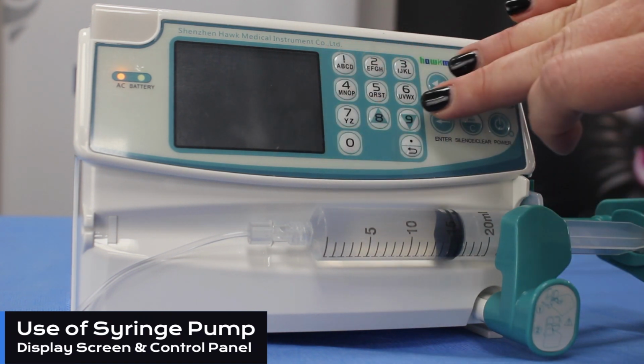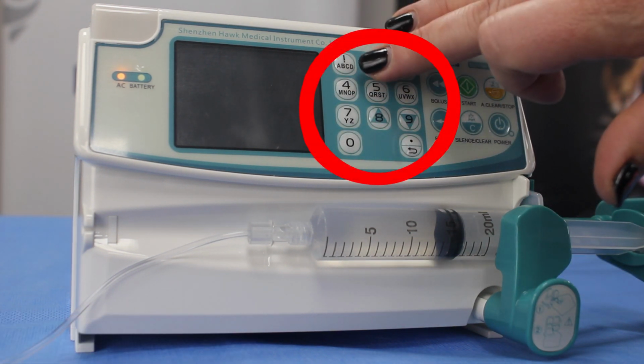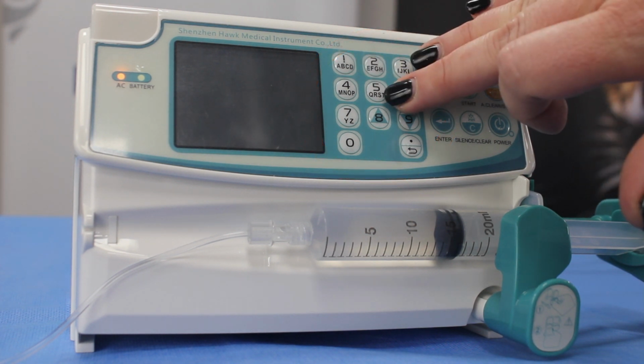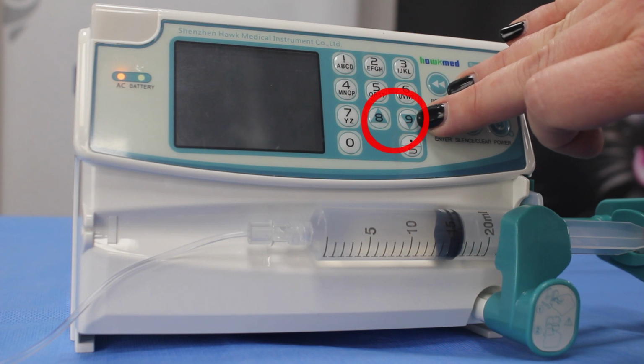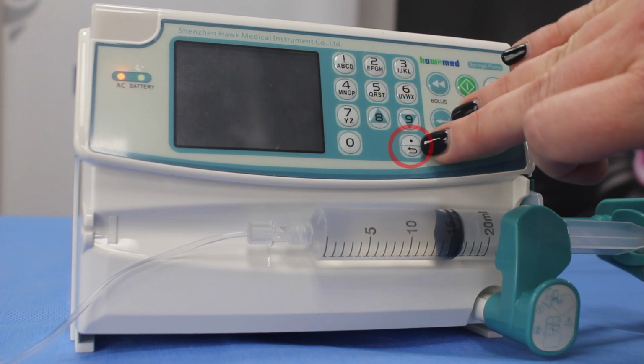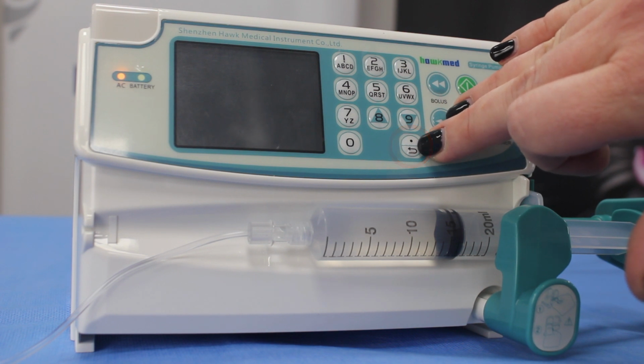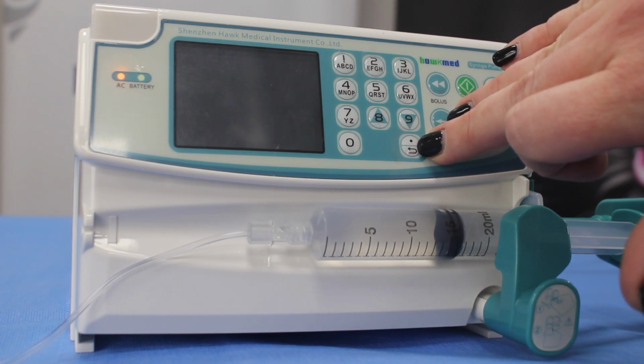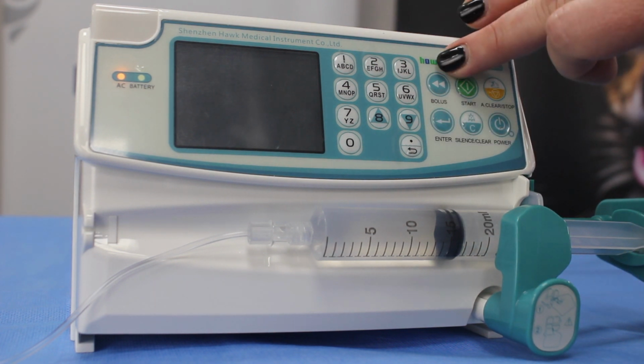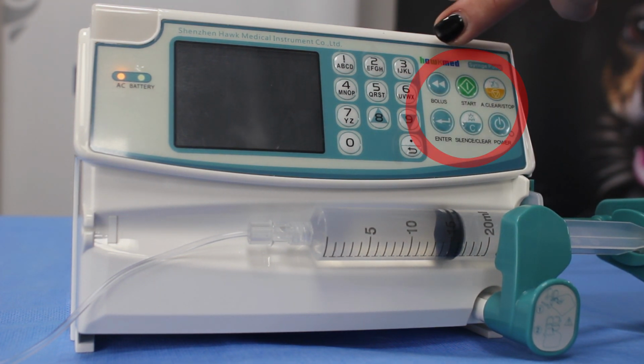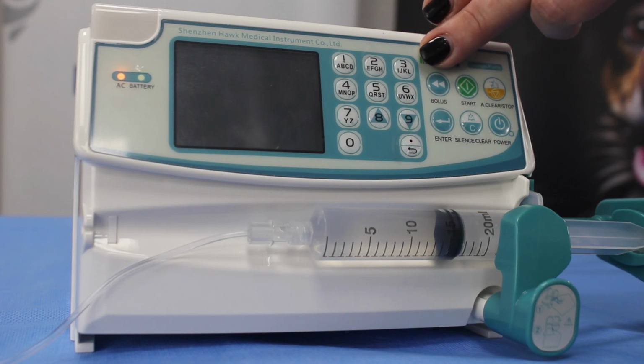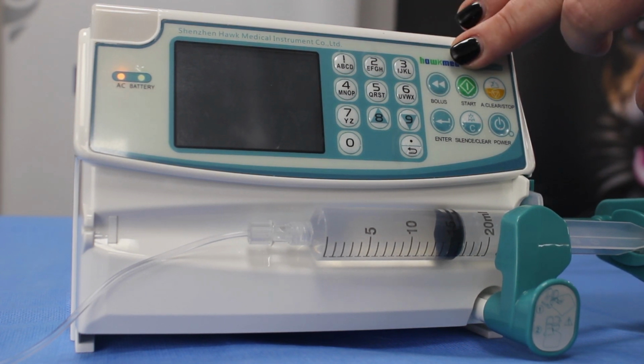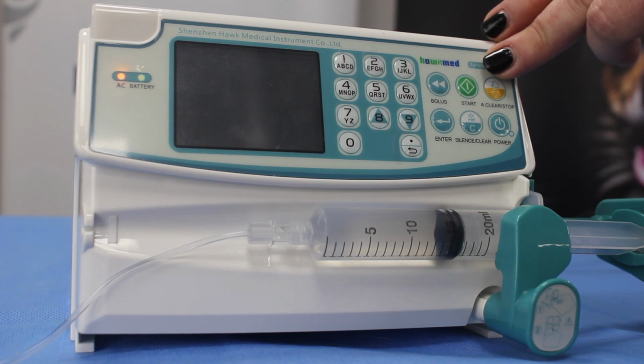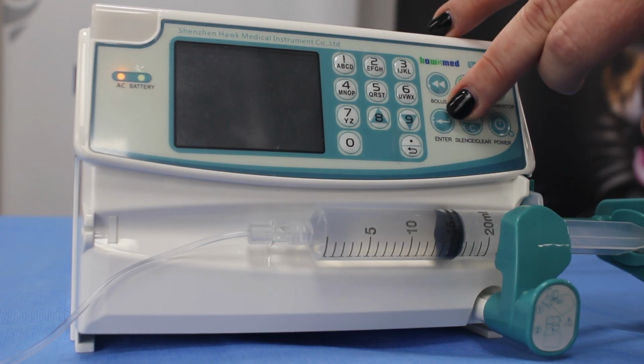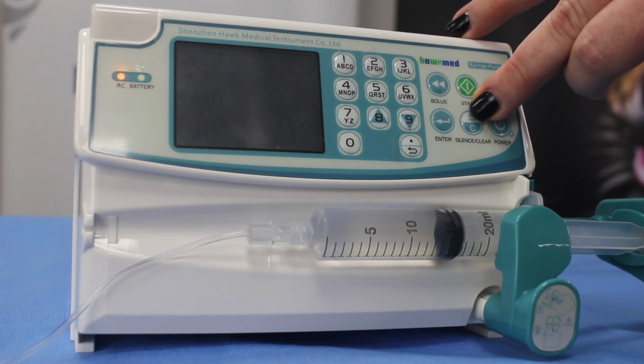Alongside our display screen, we have our number pad here, with these numbers also doubling as our letter pad as well. The 8 and 9 also double as our up and down arrows, and the decimal point also works as the back button, which we can use to navigate the menu once we've turned our pump on. Further along these operational buttons here, we have our bolus, which can be pressed and held down to administer a bolus when we're administering fluids to our patient. We have the start button, we have the alarm clear or stop button, we have an enter, silence and clear, and the power button.